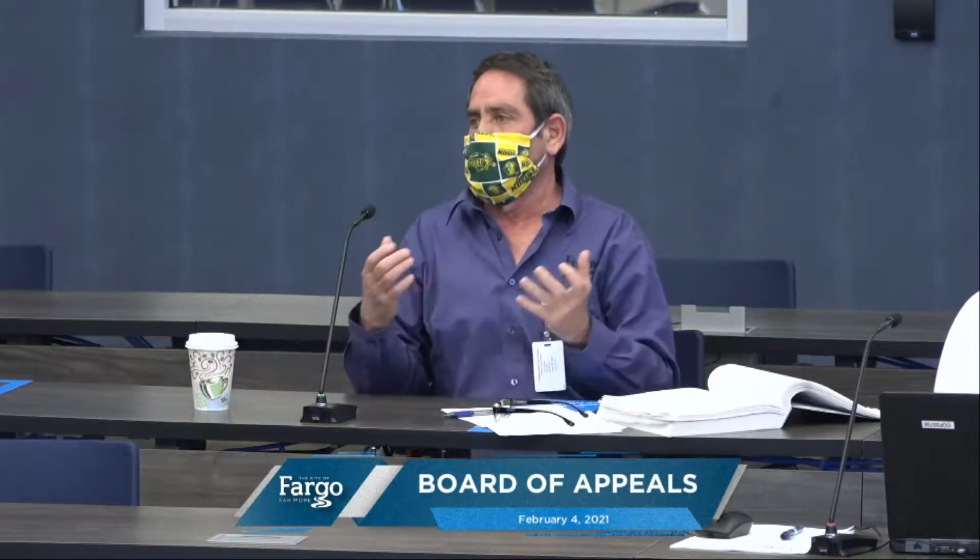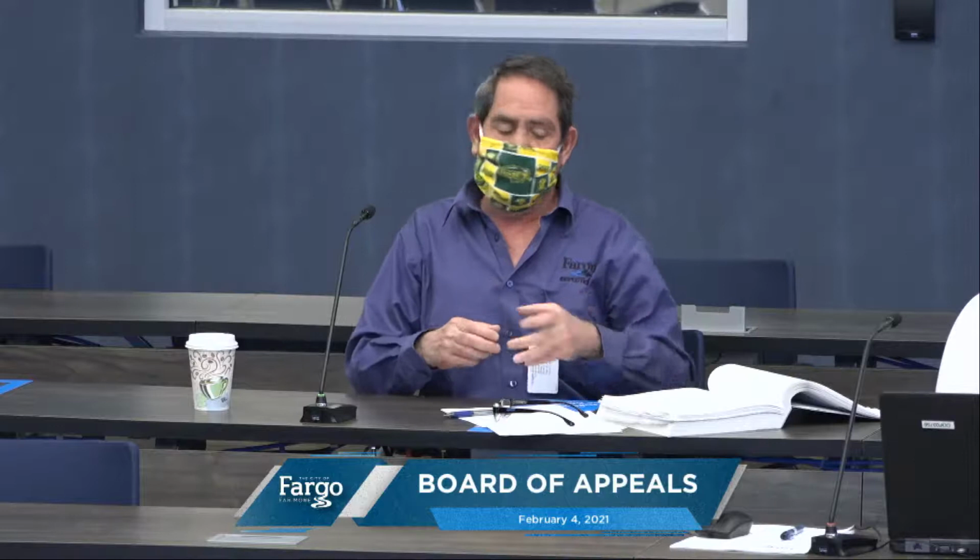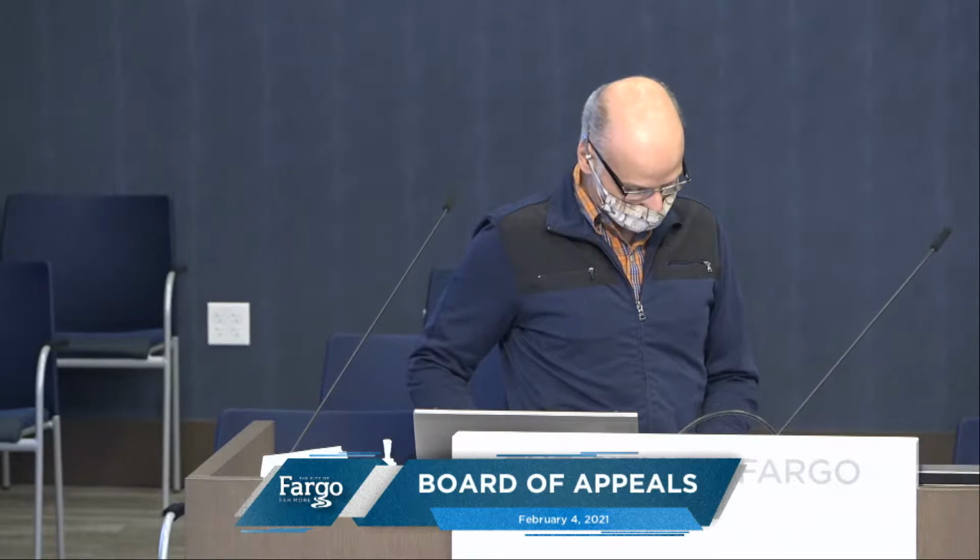1,200 square feet of open garages in a typical apartment building, that's a string of garages on the side of the lot, you are correct. And that boils down to the fire barriers and Brian's comments about where does this fire barrier stop, right? If it's open to the sky, it's okay. If it's enclosed in a room or a space, it's not okay. That's my opinion. But 406.3.1 permits it up to 1,000 square feet. I mean, it specifically permits it. Multiple private garages are permitted in a building.